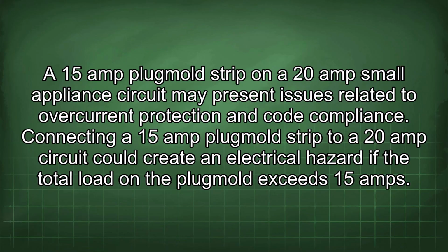A 15 amp Plugmold strip on a 20 amp small appliance circuit may present issues related to overcurrent protection and code compliance. Connecting a 15 amp Plugmold strip to a 20 amp circuit could create an electrical hazard if the total load on the Plugmold exceeds 15 amps.